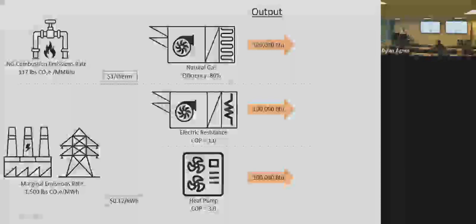So I want to compare three very simplified technologies to illustrate this point. Say you have a natural gas furnace or boiler that's about 80%, so atmospheric, non-condensing. You have electric resistance, either zonal or other electric resistance heat, which we actually still see quite a bit. And then a heat pump with just an average COP of 3. So, very basic across the board. Let's say gas costs about $1 a therm and the electric rate's about 12 cents. Probably a little higher than here, but I think the spark spread, the difference between the two, is probably pretty similar.